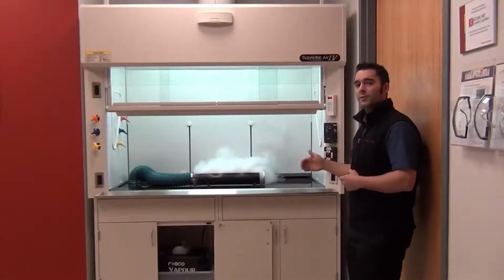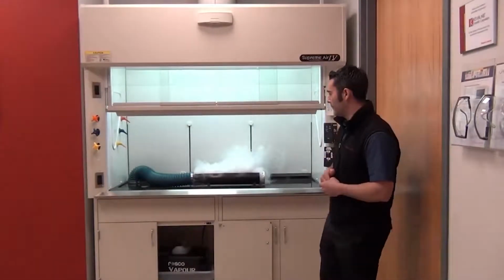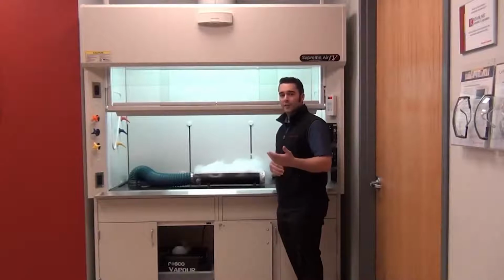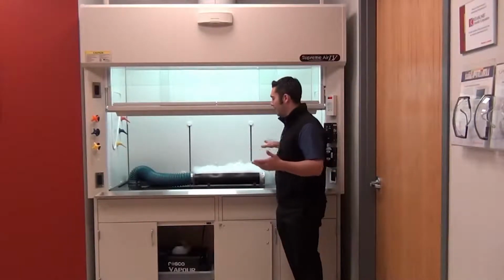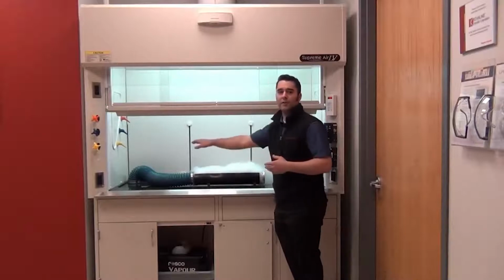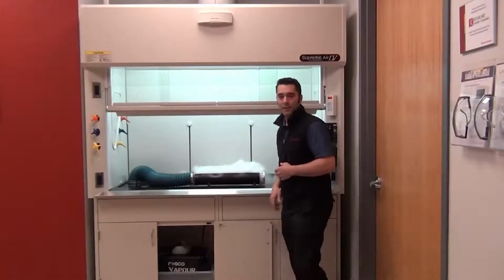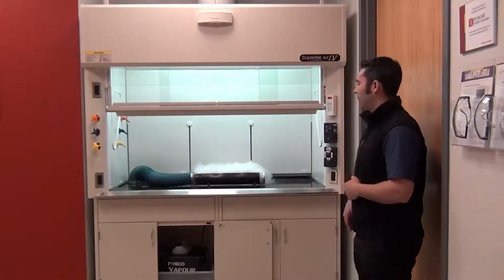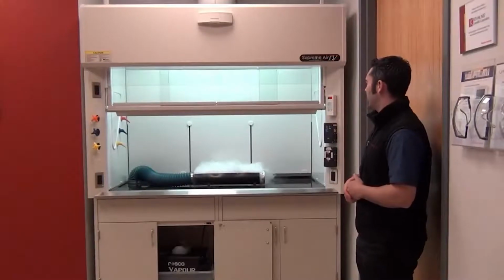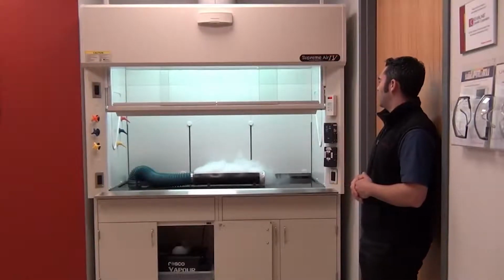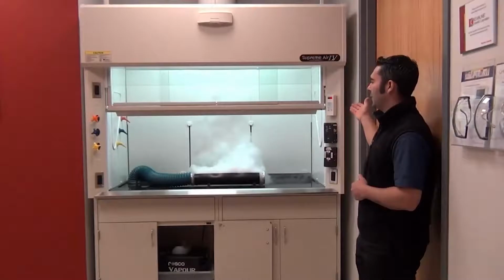Now watch what happens when I step inside of that motion zone. Within a second, again, my valve is going to go up to its full flow, 100 feet per minute, and as I move my hand back and forth in this hood, I still have no loss of containment. So again, as I step back, within 5 seconds on this particular hood, it's going to go into setback mode, and it just dropped down to 60 feet per minute.